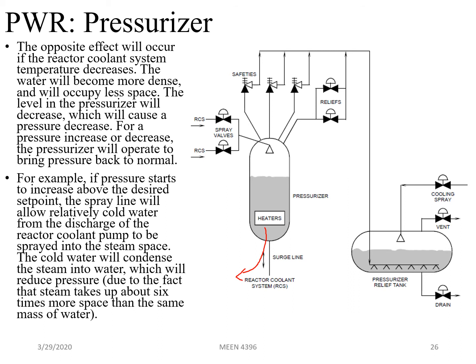For either pressure increase or decrease, the pressurizer will operate to bring the pressure back to the normal. For example, if the pressure starts to increase, on top of this pressurizer you see that there's a nozzle, and this spray line will allow relatively cold water from the discharge of the reactor coolant pump to be sprayed into the steam space. Here the steam is maintained at a relatively higher temperature, so if you spray the cold water into this steam, you are going to condense some of the steam back to water. If the steam is condensed to water, then it will occupy less volume. In that case, the pressure is going to decrease.